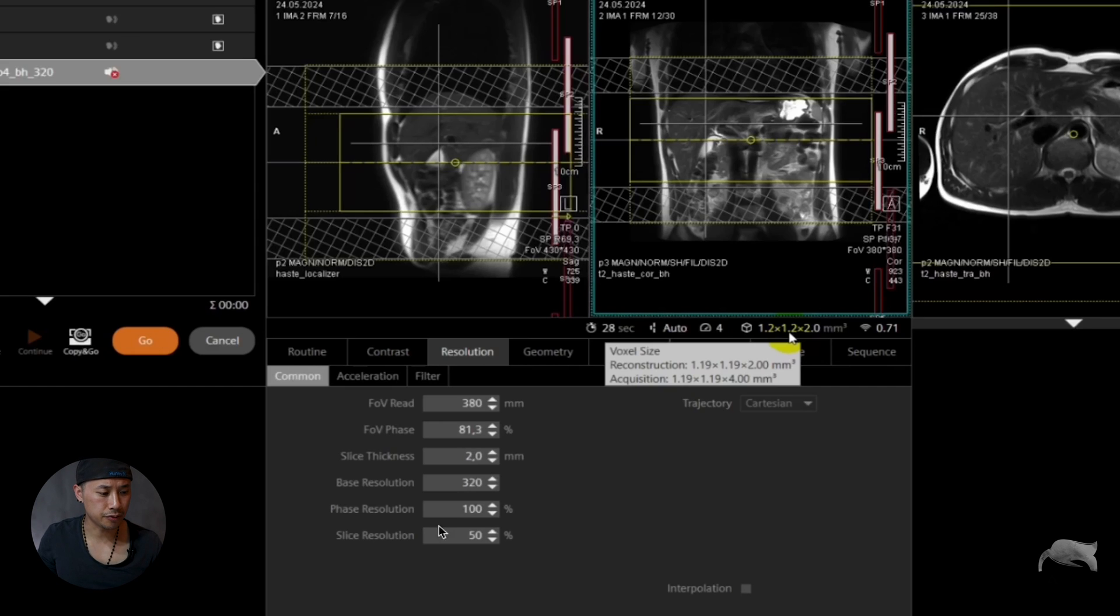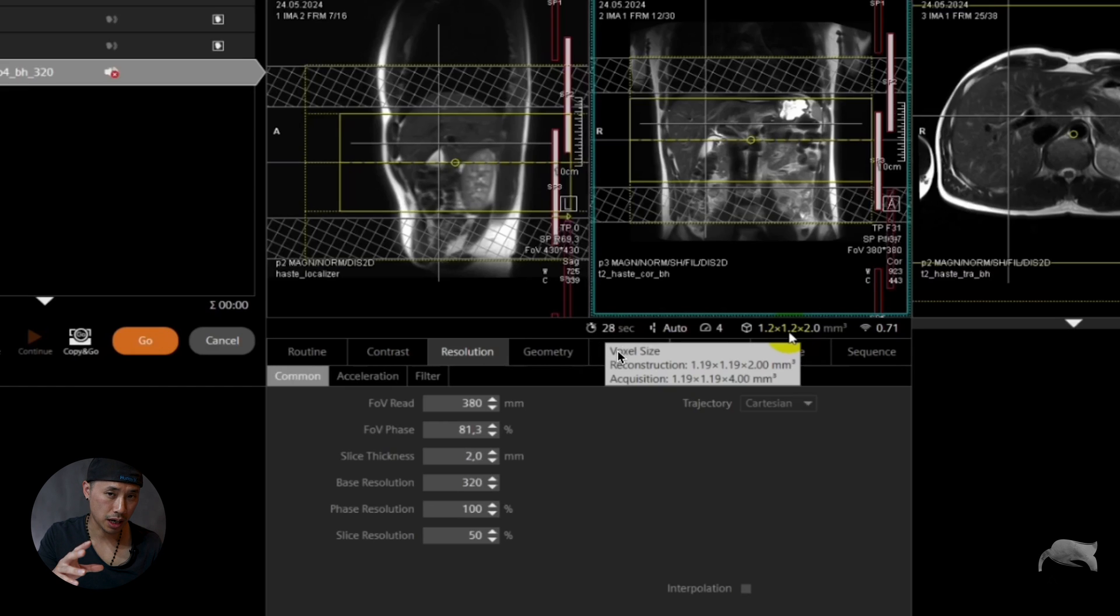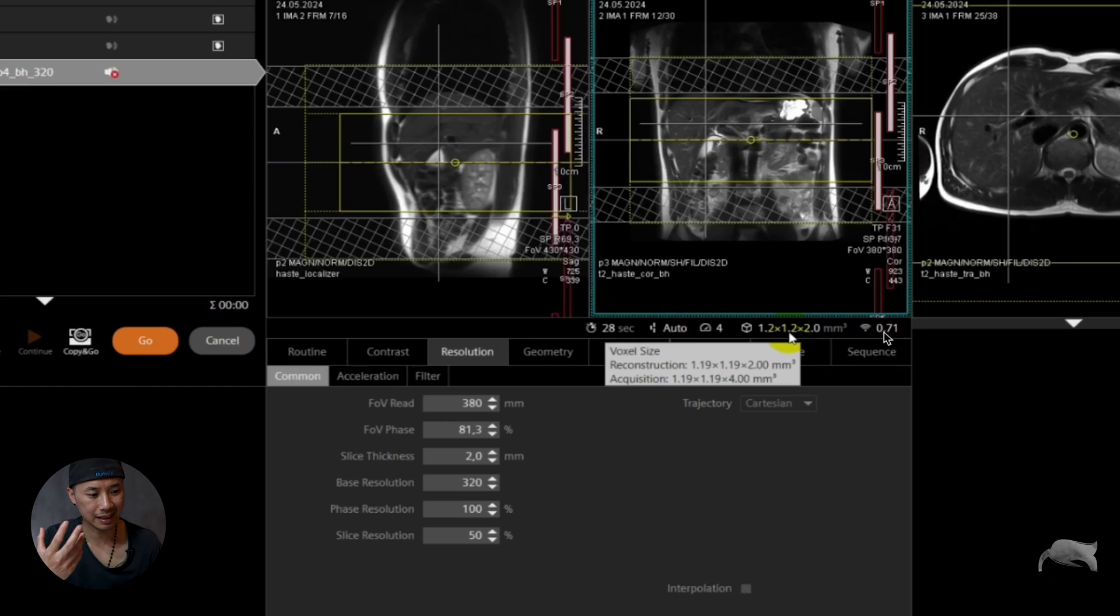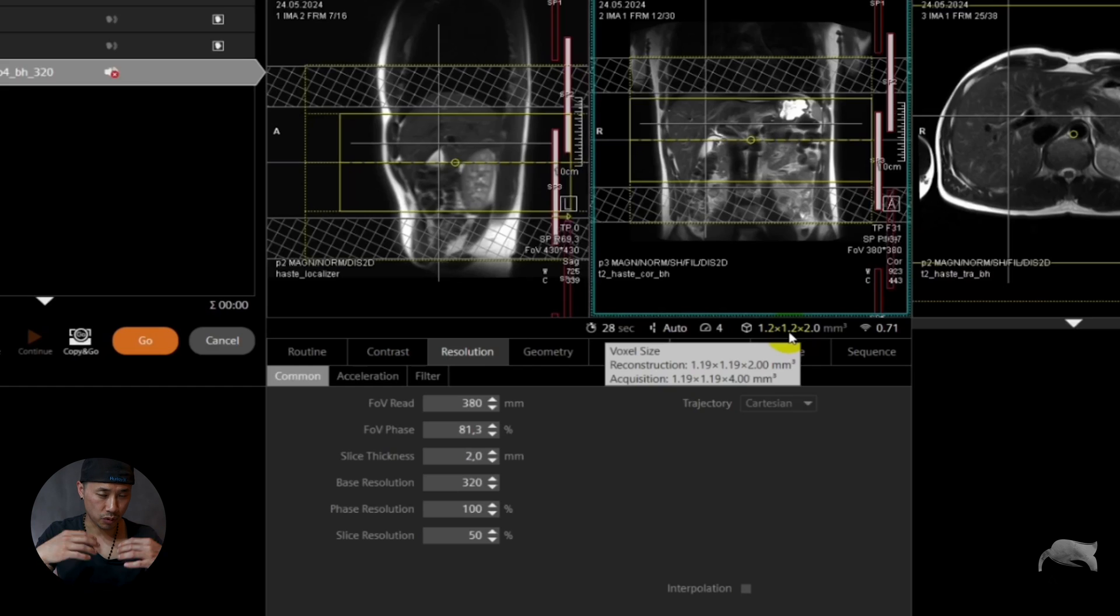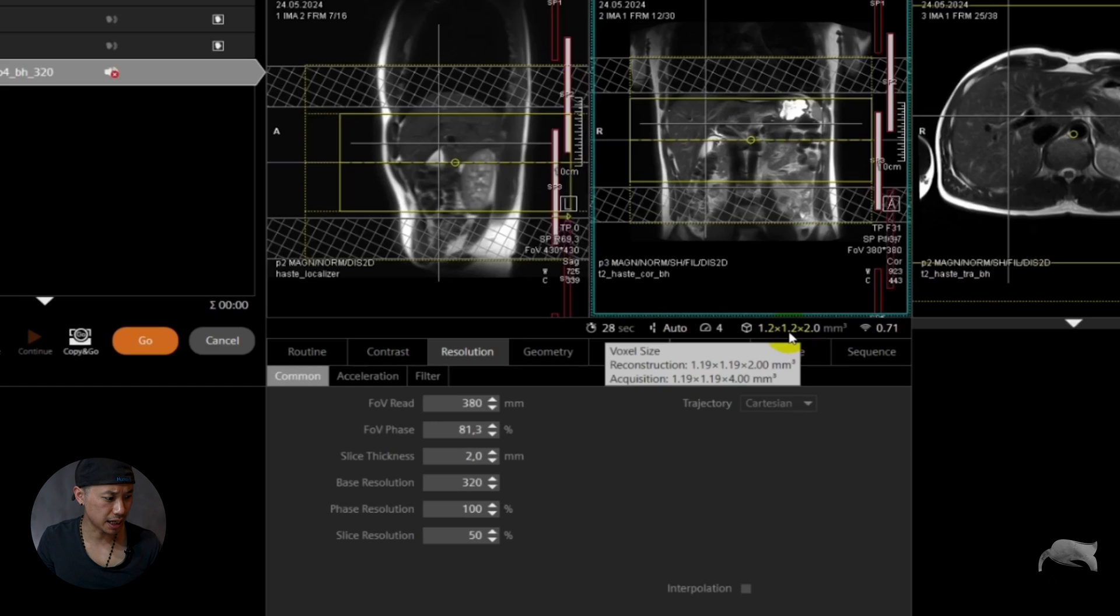And then the scan time, it's still too high. We went from 36, now we are 28. We gain a little bit more SNR. The reason for SNR is that the voxel sizes are a little bit bigger so you get more SNR, right? But we can also see that we need more slices.